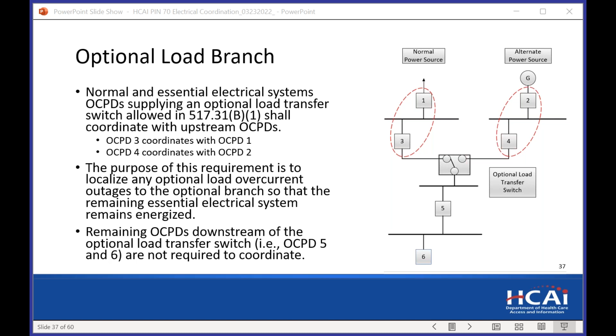Yeah, my general thought is that if you're backfeeding, then you're opening the main breaker and you're using that as a temporary power flow, in which case you wouldn't have to coordinate with the breaker that's disabled. Yeah, I would tend to agree, but there has to be more to it than that. Great. All right. Submit that question, and Bill, if you'd like, you can move on to the next section.